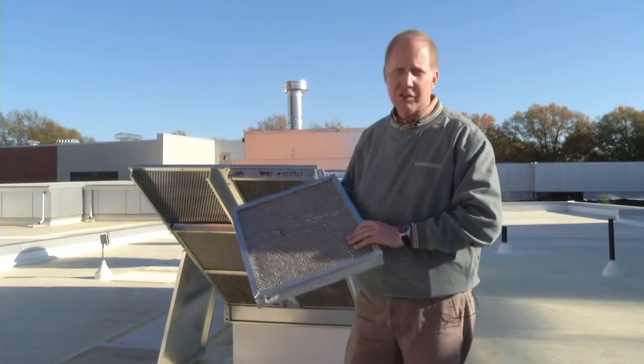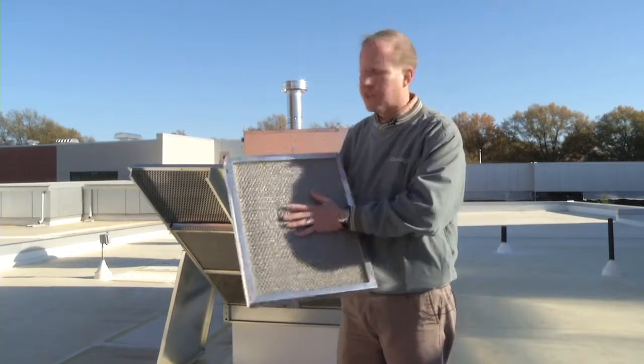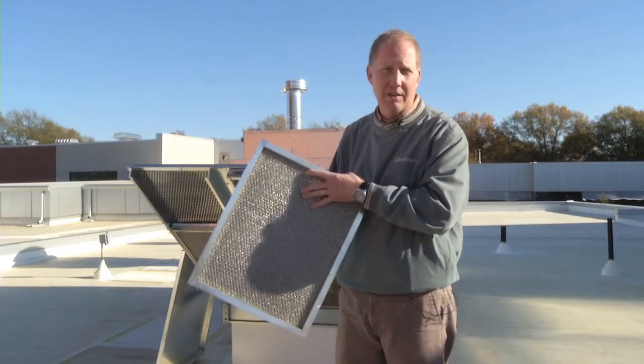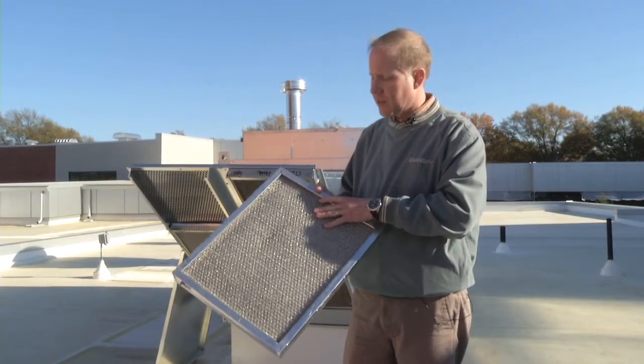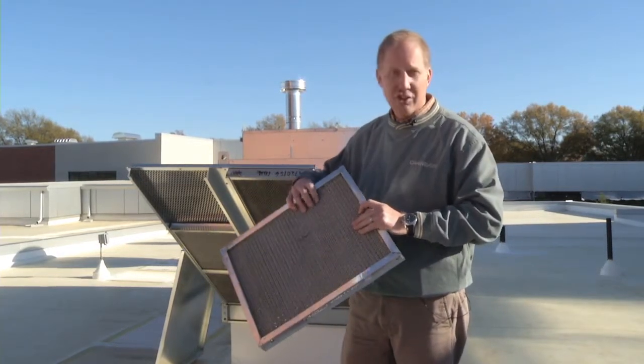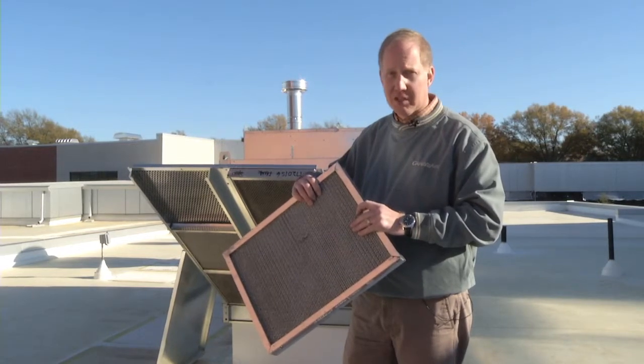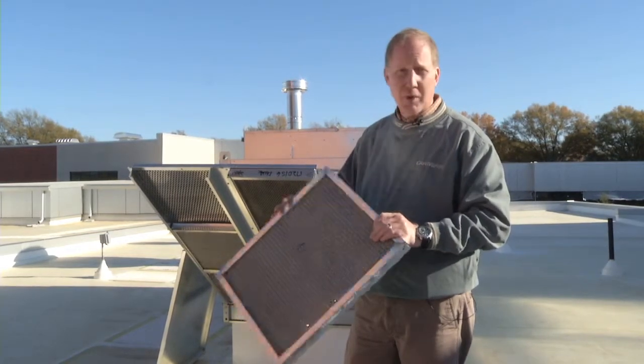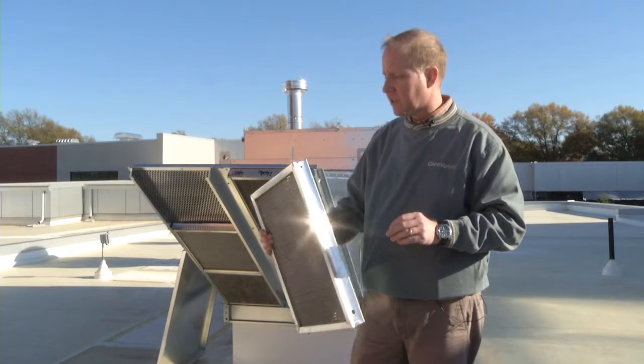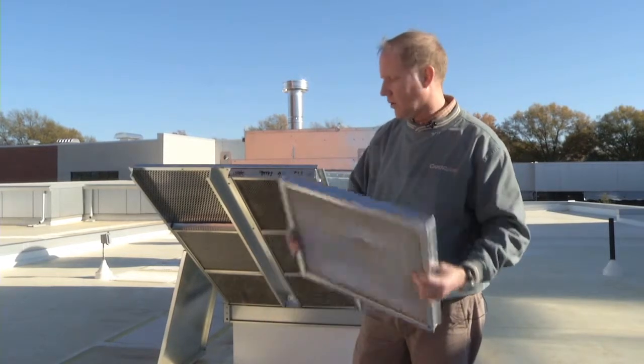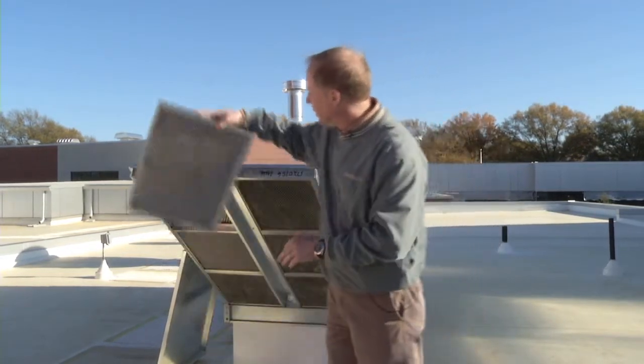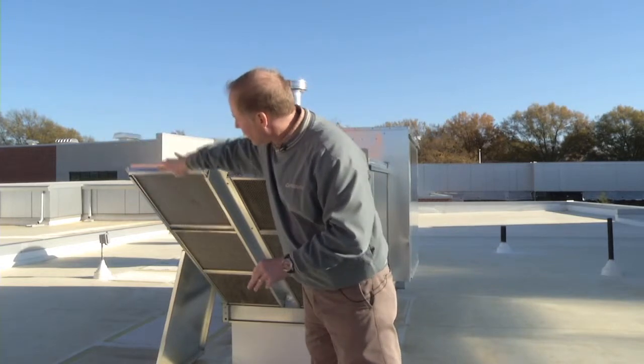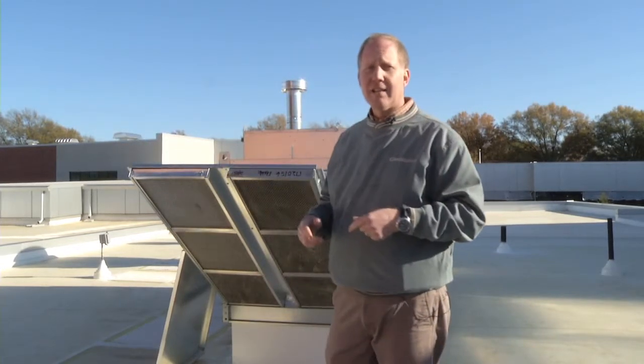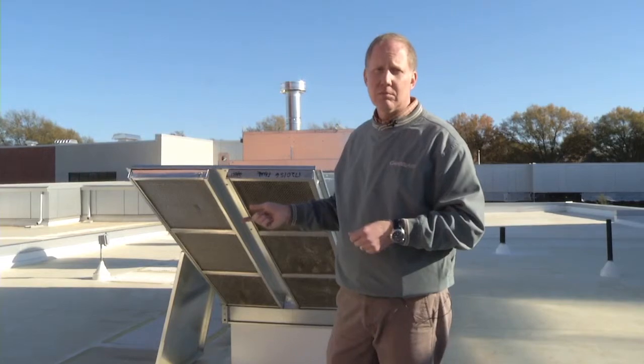These can be washed. Be careful with a pressure washer. If it's too much pressure, it will knock out the mesh, if you will. It can loosen this material. Other than that, a light spray with a degreasing formula and they go in very simply. Now we're going to take a look at the controls side of this unit, and I'll join you there.